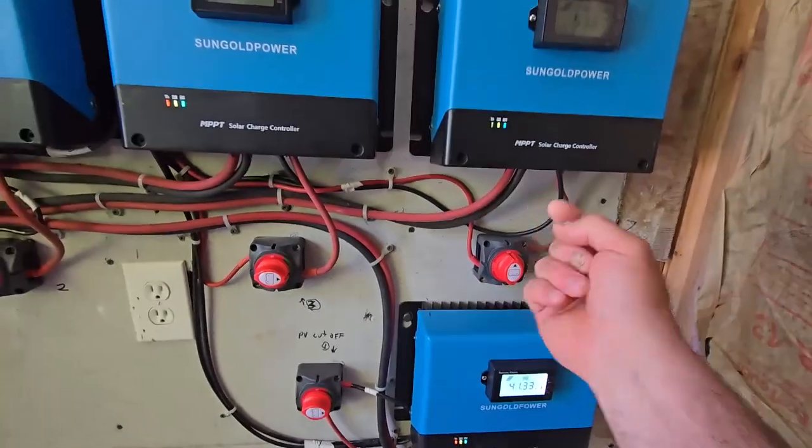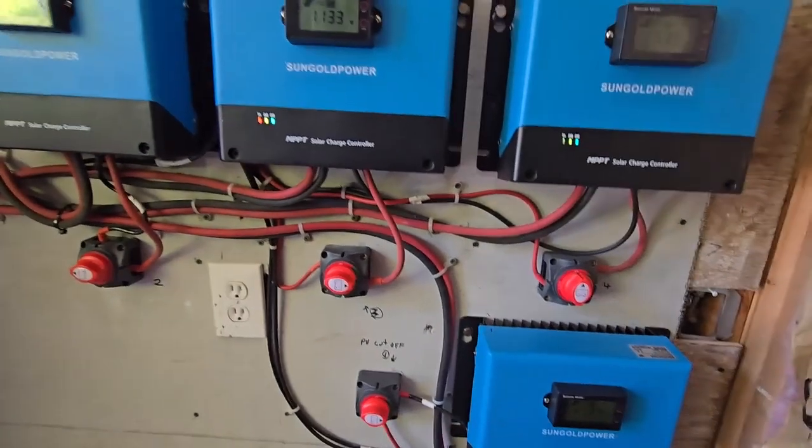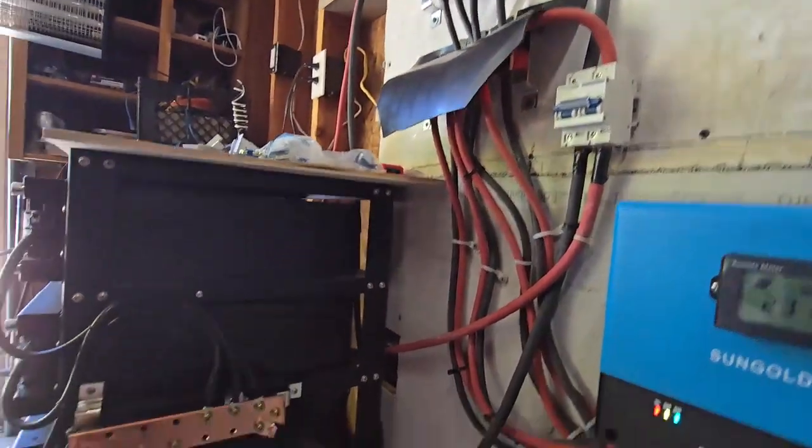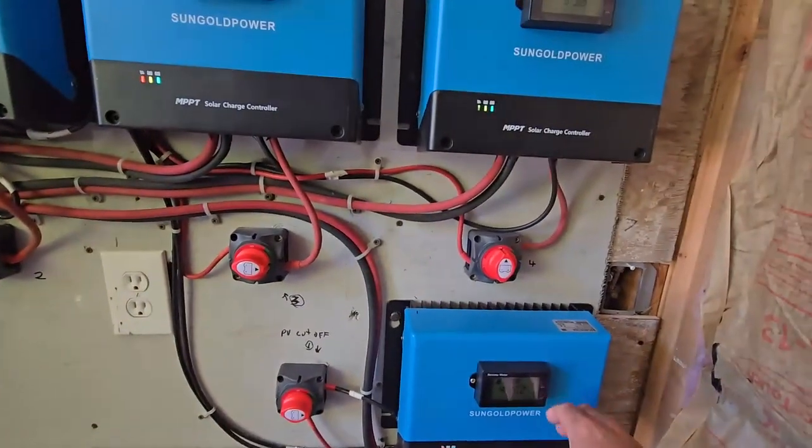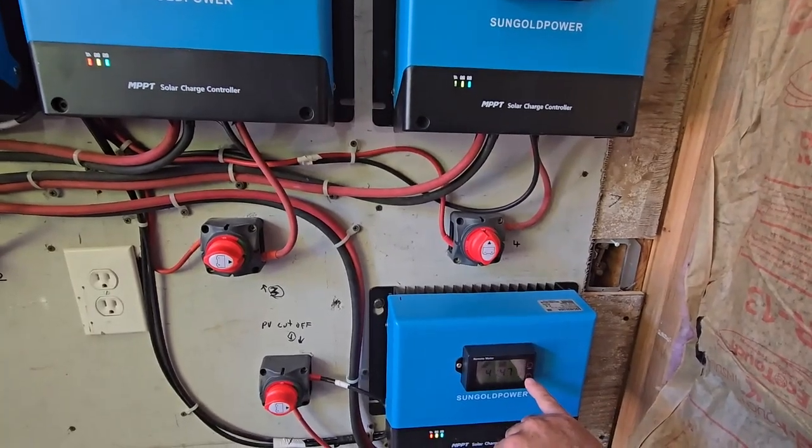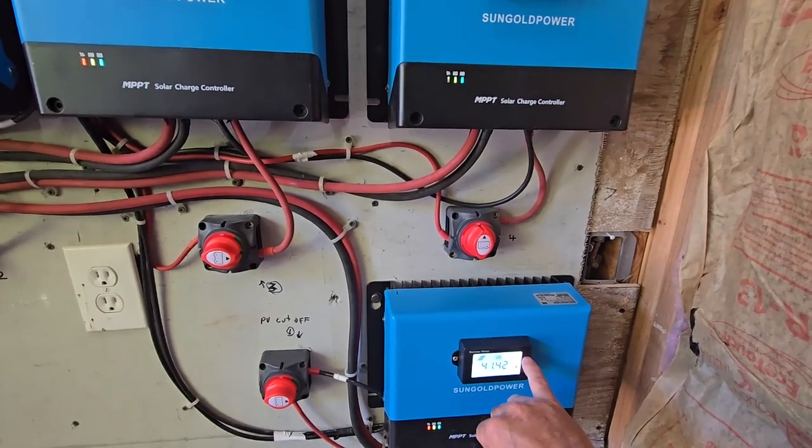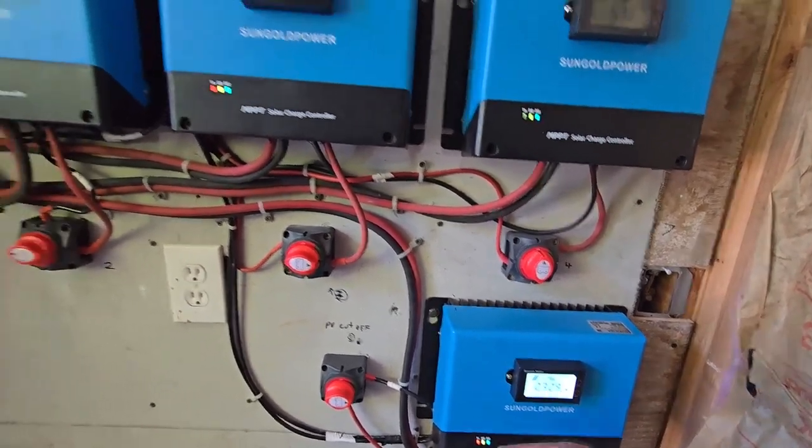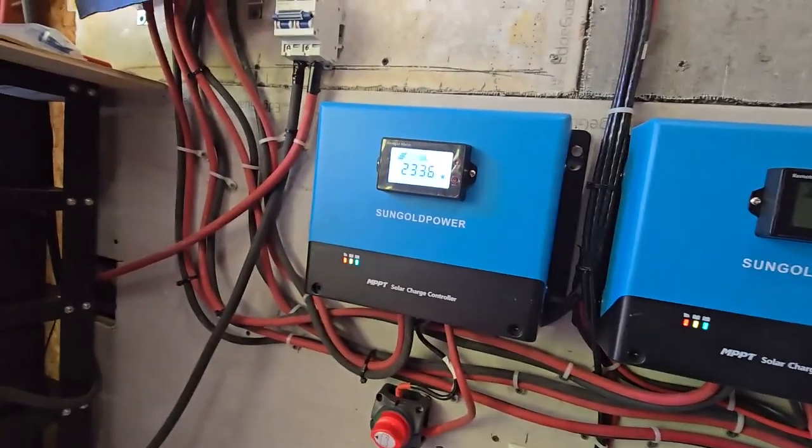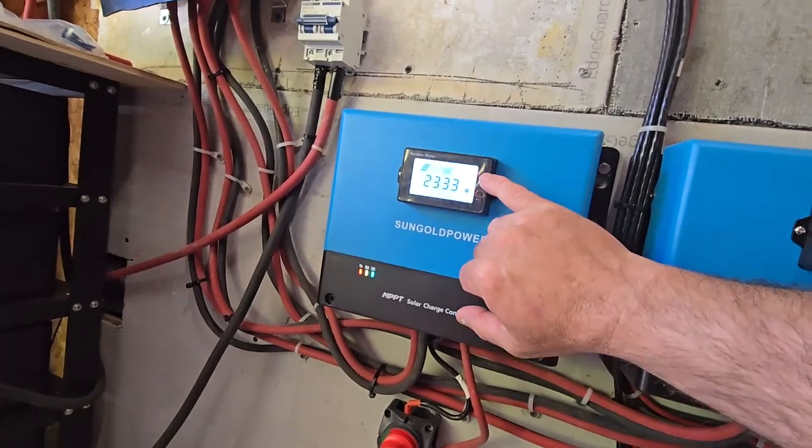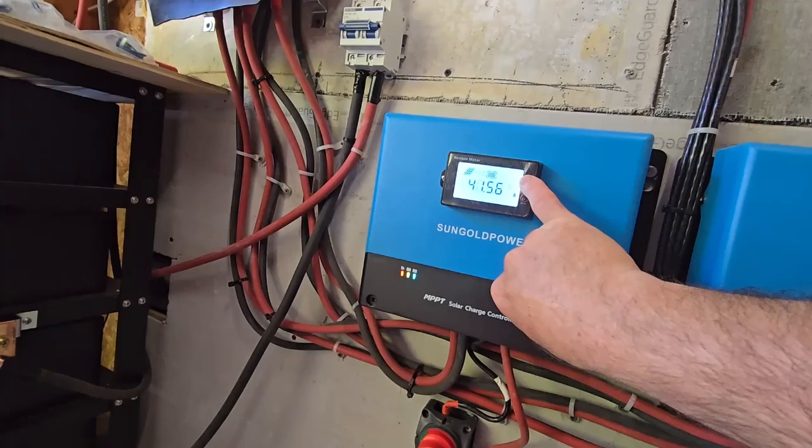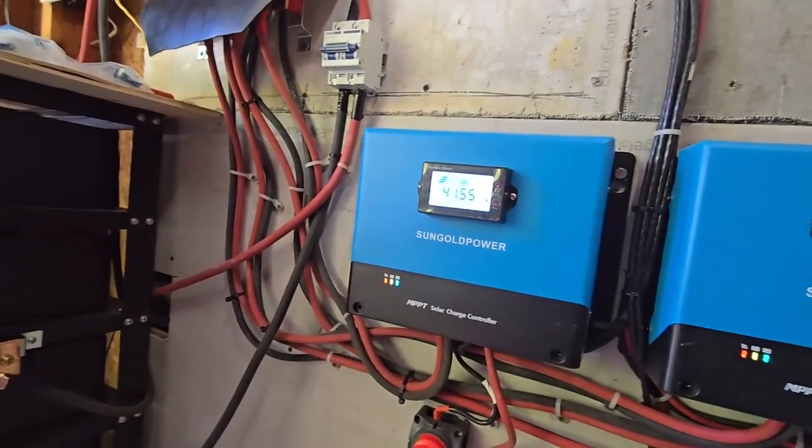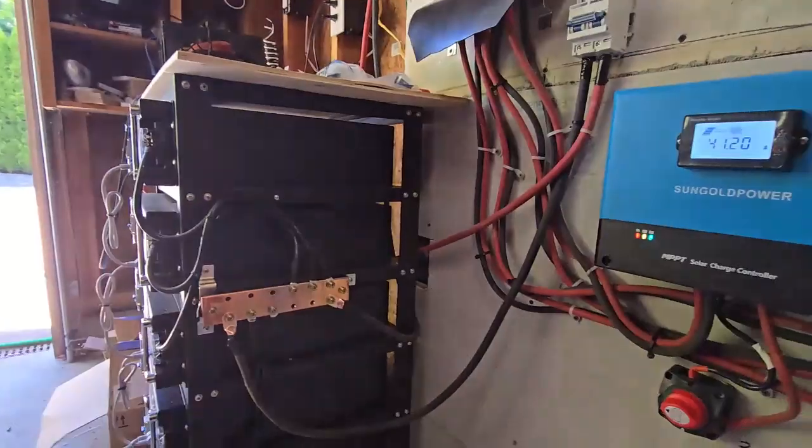So it's basically producing all the power out these main big cables up to the bus bar up here that then feeds to that breaker and goes into the bus bar on the battery bank, charging the batteries. So this one, like I said, is producing 41 amps, DC power, and right now we're at 2,300 watts. Number two is this one. It's producing also 23, 36, about the same. So it should also be producing about 41 amps. So right now that's 82 amps going into these, charging these DC batteries.